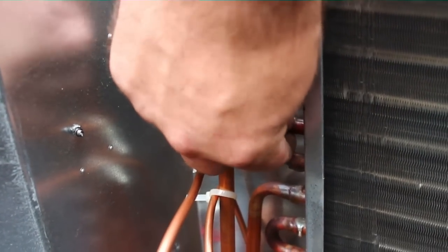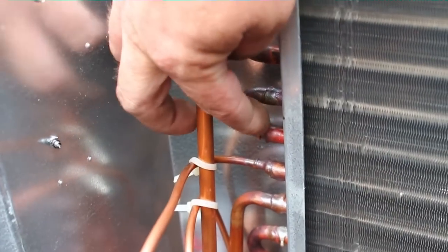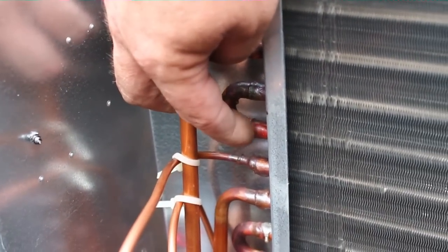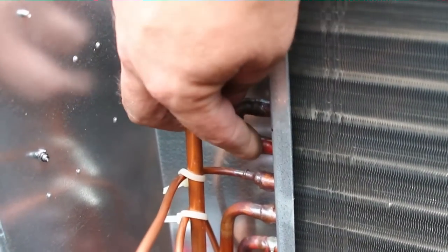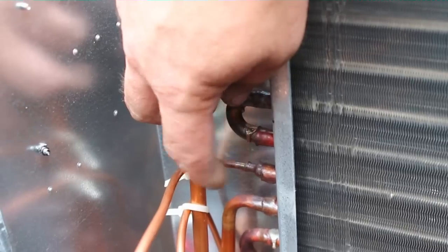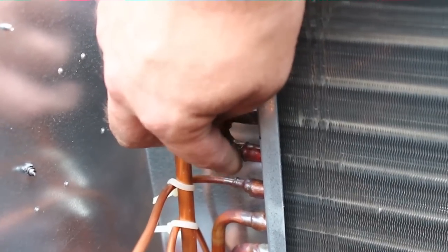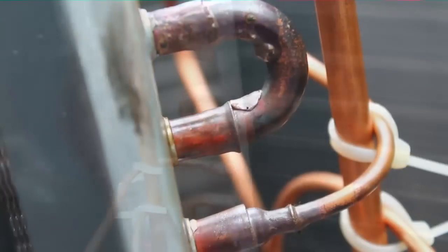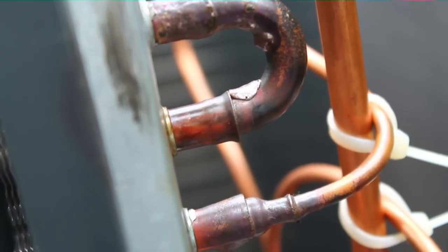I did a nitrogen test on it, and you can actually hear it leaking. I don't know if you'll be able to hear it here, but you can see there's a little bit of sloppy brazing right there anyway. So we're going to rebraze that U-bend, and that should be the only problem we have out here with this unit. And that's totally worth 80% off. This is the view from the other side of the U-bend. You can see it just looks like a very sloppy joint.